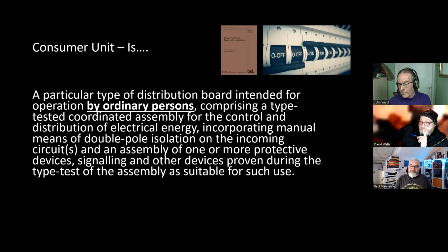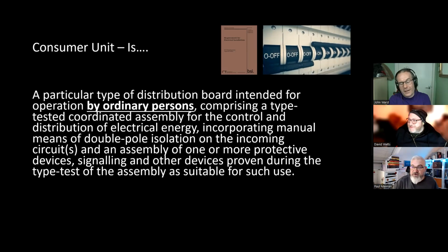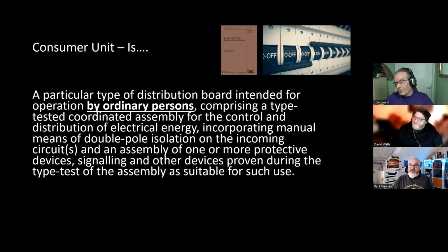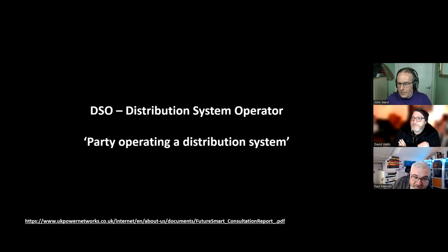Yeah, whether that was the intent is another matter. That's certainly what it suggests. They're probably in the office going, "Oh, for God's sake!" Yeah, bloody hell, what's wrong with you? But the important thing to add with that one is it does say type tested, type tested, type tested. So if you do decide to swap devices from one manufacturer to the other in your consumer unit, it might no longer be defined as a consumer unit. Well, it won't be, because the minute they brought this type test rule in, and that mix and match stuff, now under this they've just said, well, it's not a consumer unit under the standard. Exactly. By the definition, it's not a consumer unit.